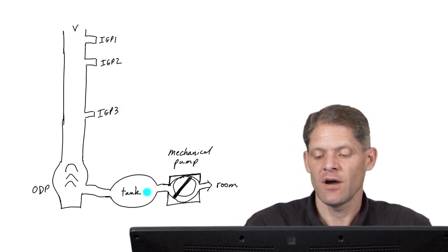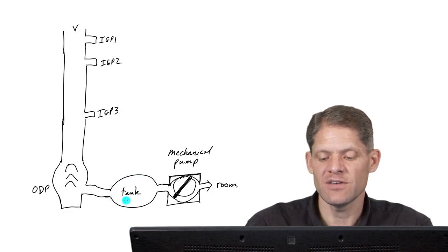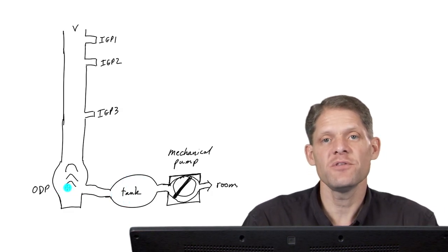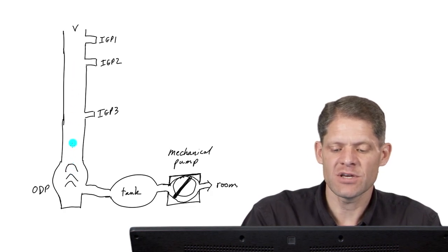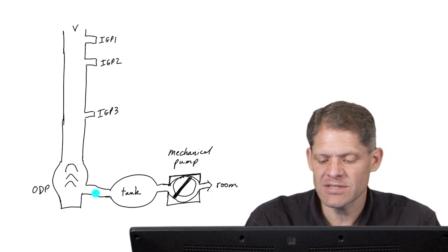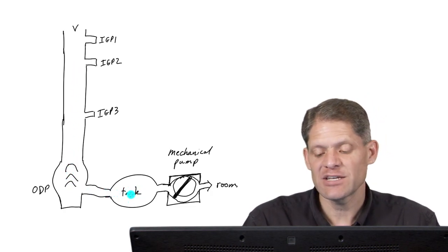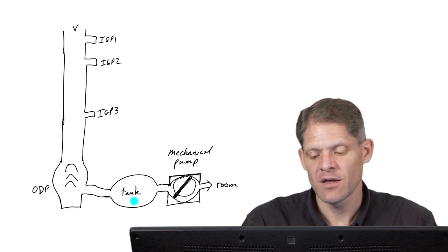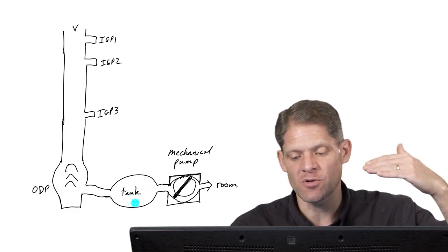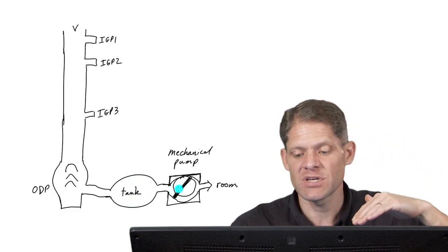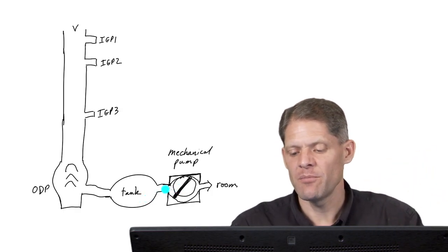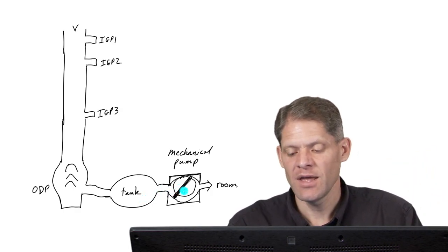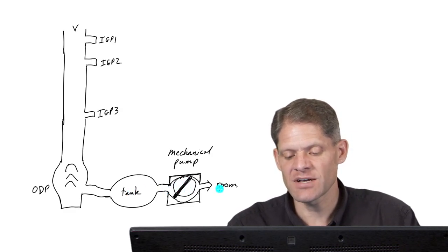Once it's achieved a strong vacuum in these regions, then the oil diffusion pump is turned on, and it further evacuates the column and pushing its exhaust into the tank. As pressure builds up in the tank, once it reaches a certain threshold where the mechanical pump will once again be effective, sensors sense that pressure, the mechanical pump turns on, it pumps down the tank and exhausts that into the room.